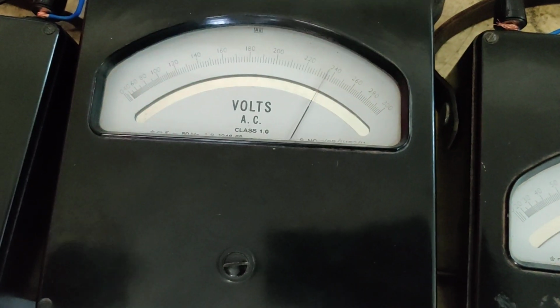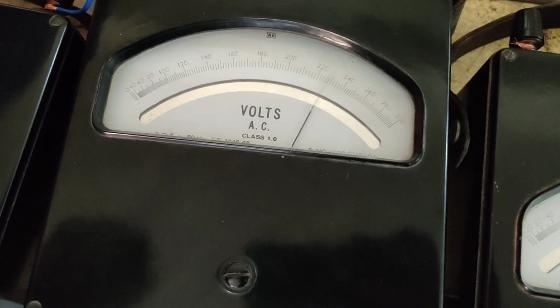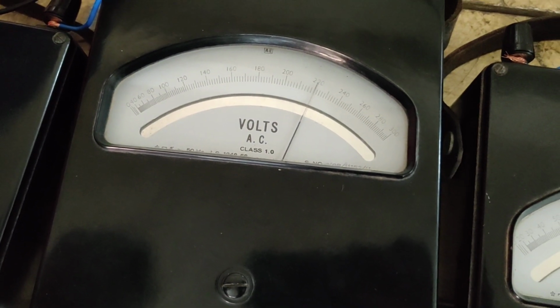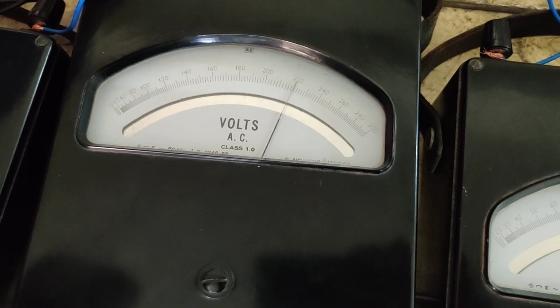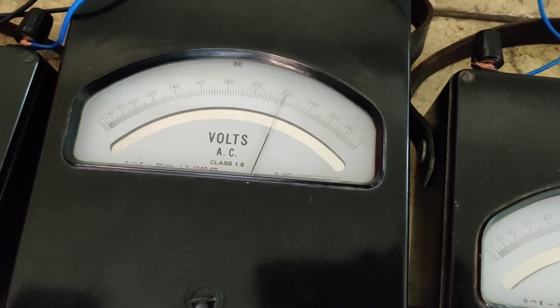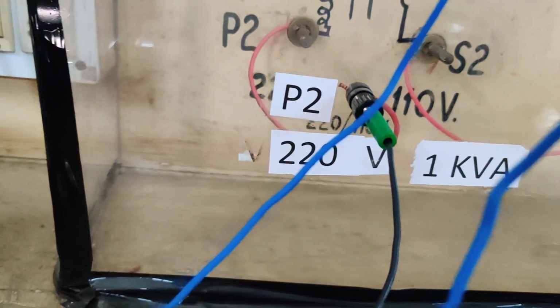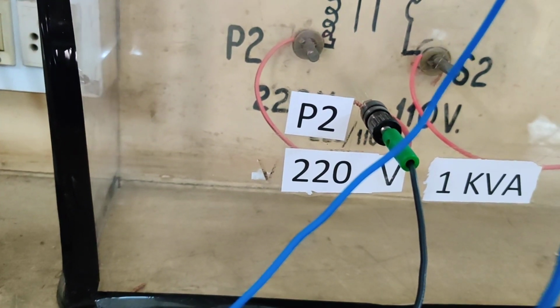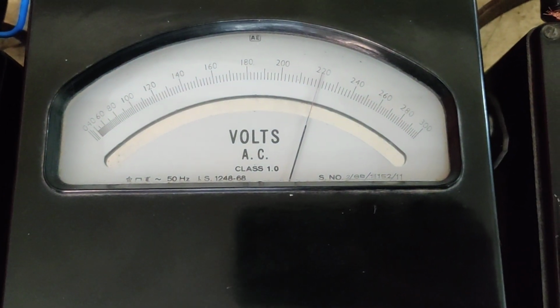We have to maintain this at 220, because although in single phase we have 240 volts available with us, the problem is that in this transformer the primary side rated voltage is 220 volts. That is why we have to give 220 volts here.